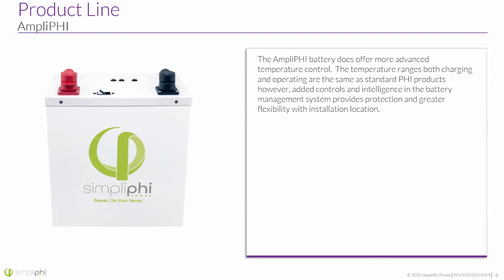The interesting part about the SimpliPhi and this feature, which is actually really important to note, is that this feature works off operating and charging temperature. So since the operating is allowed to go a little bit lower, this BMS actually knows when you're discharging. It'll allow you to discharge lower. And if the charger tries to turn on, only then will it disconnect. So you can get a little more juice out of the battery, even if it's pretty cold, as long as you're not charging. But again, that protection's built in so that if you do try to, say, charge at negative 20 degrees Fahrenheit, let's say, it will disconnect the charger and make sure not to harm the battery until it's safe, until it hits that higher temperature. So it has that feature built into the battery internally.